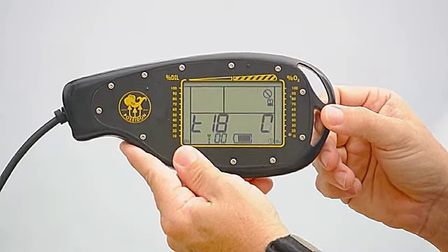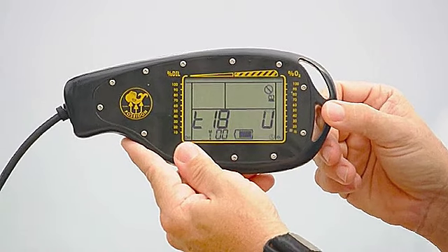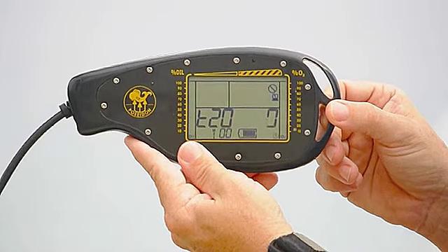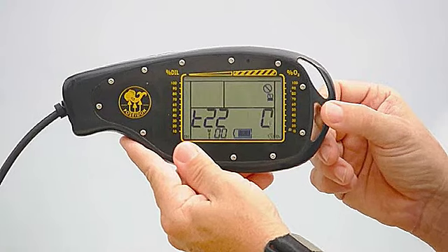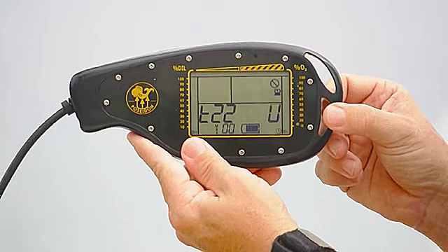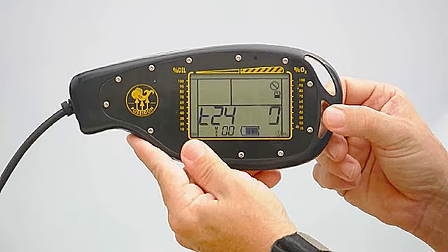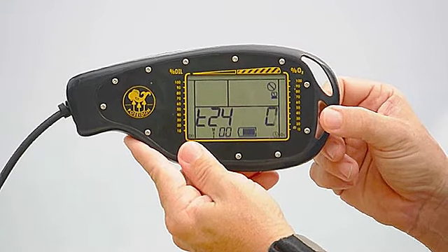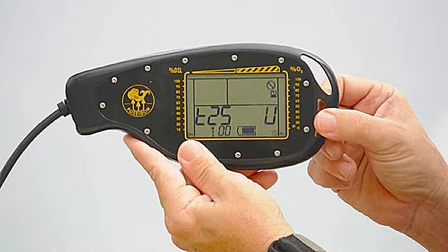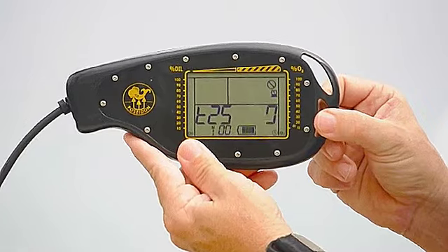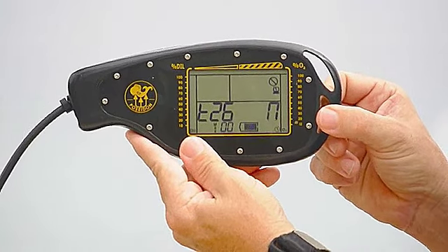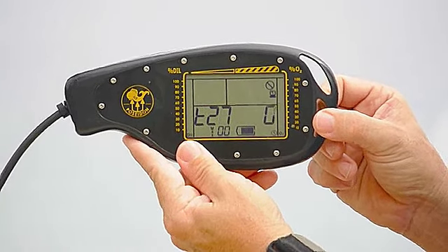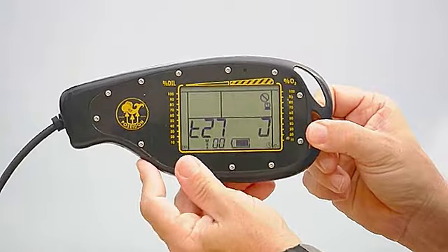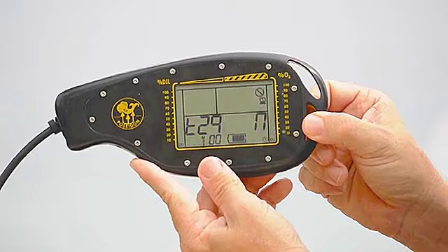The first 27 of those tests or so are internal tests that monitor whether or not the solenoid valves are actually pulling electricity, whether the alarm systems are pulling electricity. It's sort of a way of making sure that the mechanics of the LEDs and the speakers and the solenoids are actually working, because if they're not, it won't detect power draw when it tries to turn them on. So it's doing a lot of internal diagnostic tests right here.